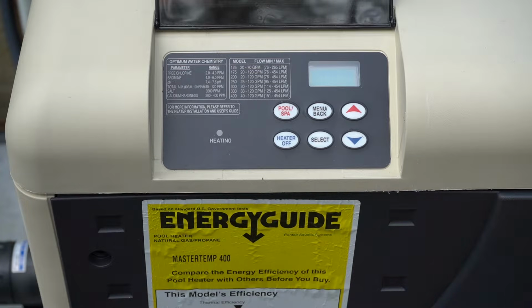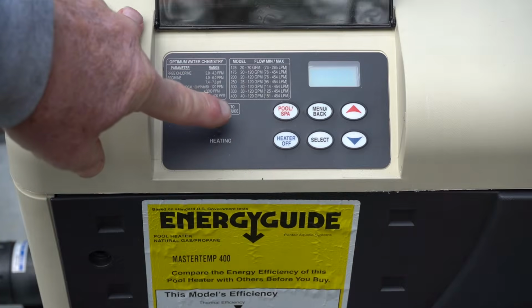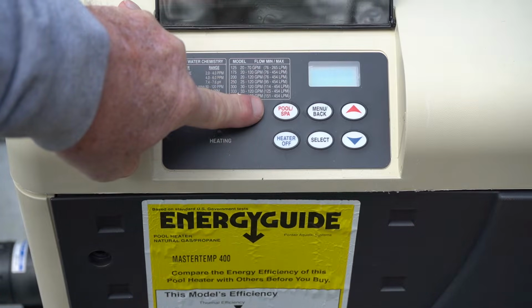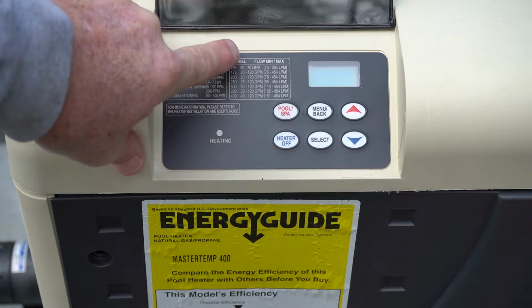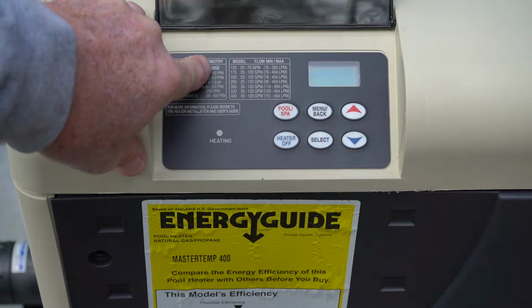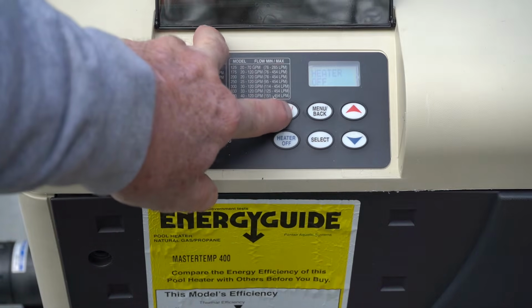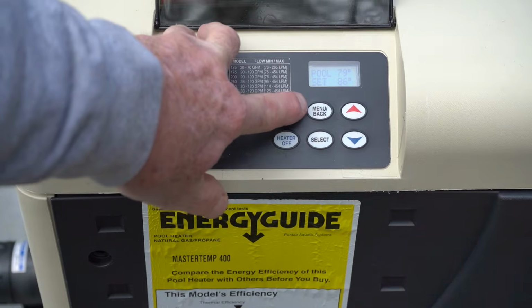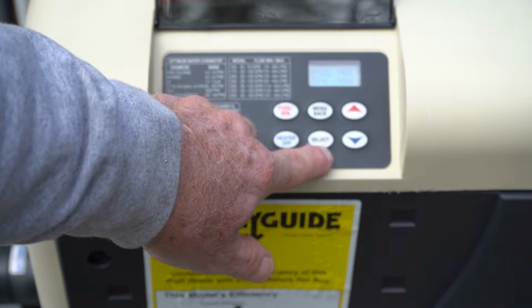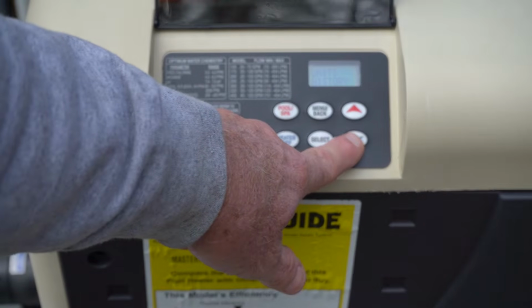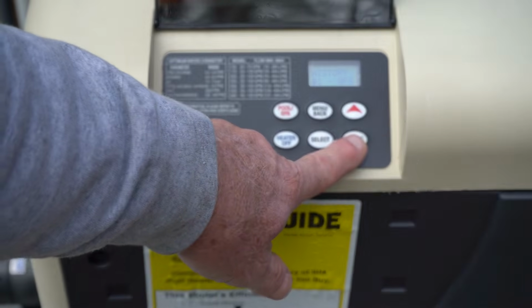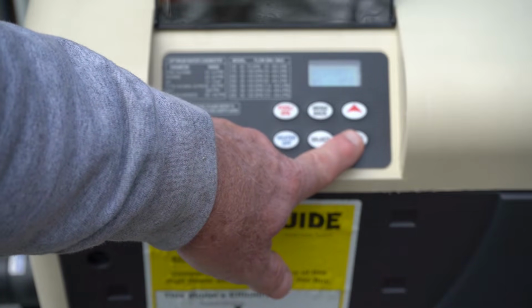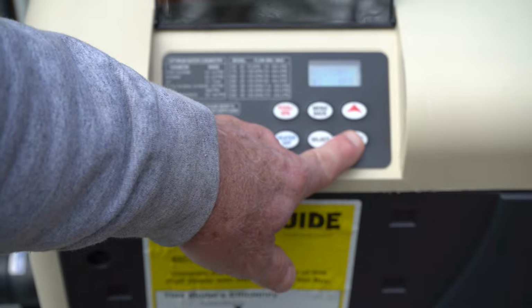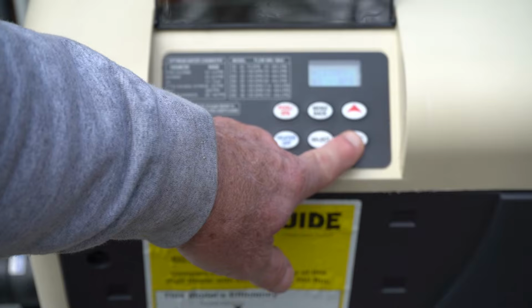A lot of times what happens is the heat exchanger gets sooted up, and when it gets sooted up it overheats and it trips the stack flue sensor. Now it is possible that the stack flue sensor is sporadic, and you'll be able to see that if it was sporadic in what we're showing you today. So the first thing we're going to do is we're going to turn this on, and then we're going to go to menu, and we're going to go down until we see history. We're going to select that, and you'll see you've got airflow sensor, and then airflow sensor, stack flue sensor. So it rotates between stack flue sensor and airflow sensor.